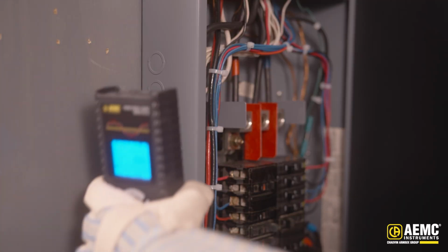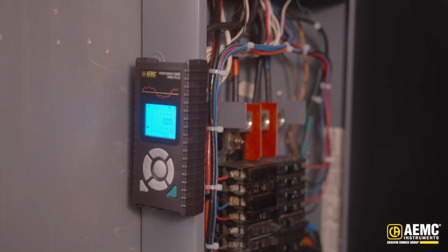With 4 strong magnets and a slim form factor, this instrument can be installed in a variety of different applications. And if we're working in an area where we can't attach it using the magnets, there's an included door hanger available. The bright display on the front panel of the instrument allows it to be used essentially as a 3-phase multimeter. We can install this instrument in a location where we can see in real time what the measurements are from the instrument at a safe distance.